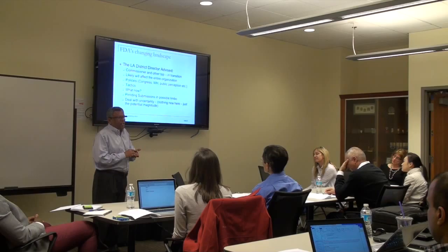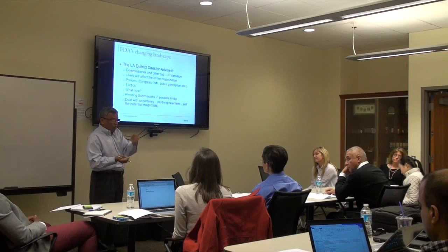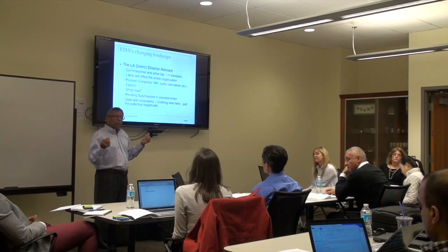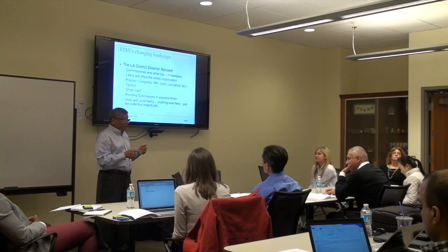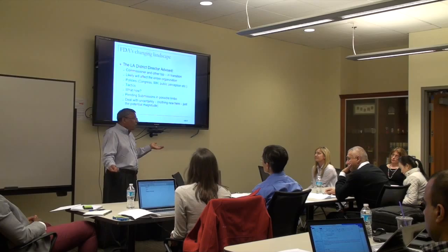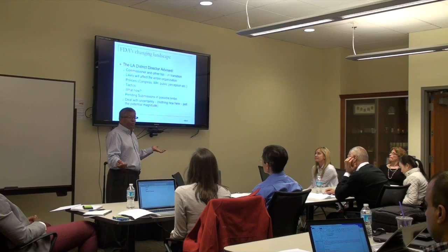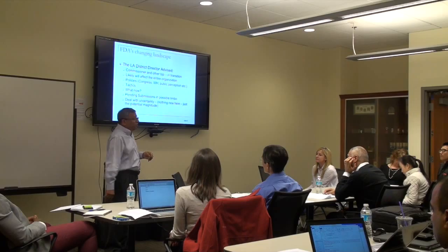For risk analysis, it's never been a formal written requirement in most places — there's only one place where you're required to do risk analysis before you take the product into a patient. Now they want risk management: where are you doing it, and how are you following it? From my experience, I put reasonably minimum information in a submission, but I have everything prepared. So if somebody asks a question, I get an email the very next day with the answer.